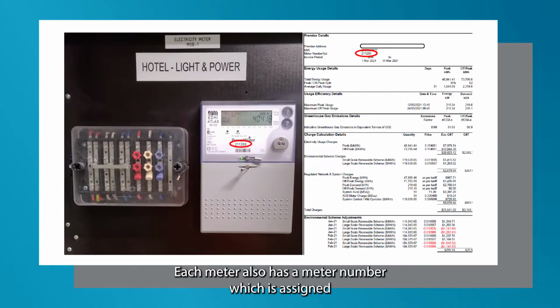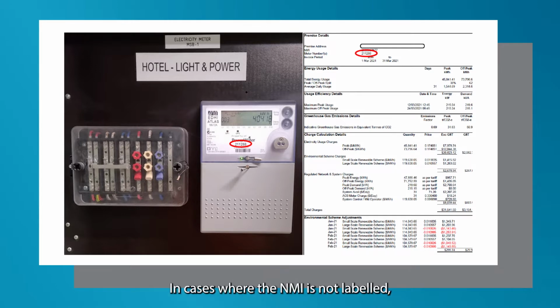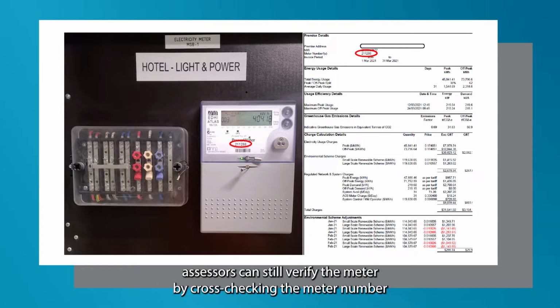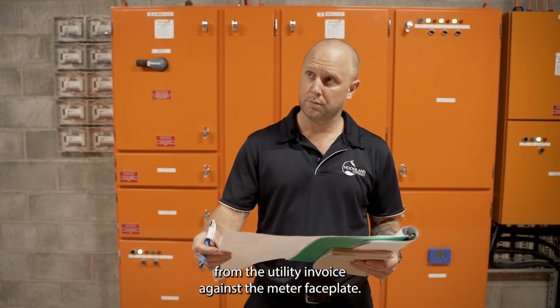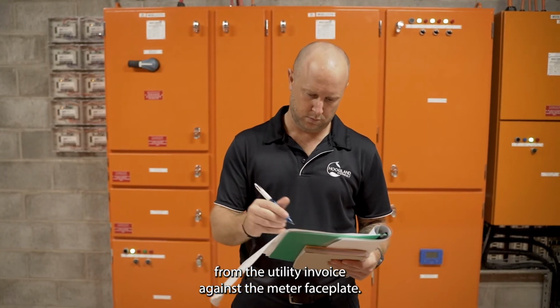Each meter also has a meter number, which is assigned by the meter manufacturer and is separate to the NMI. In cases where the NMI is not labelled, assessors can still verify the meter by cross-checking the meter number from the utility invoice against the meter faceplate.